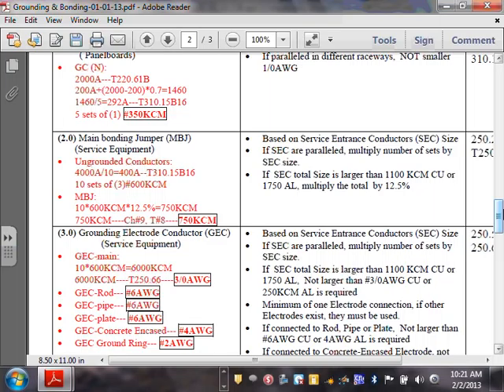Then you have to have a lot of fittings though. Clamps, I guess if you have a clamp, it's not a big deal. You just land it with a clamp. But remember, you're inside the bottom of the switchgear, and the bottom of the switchgear is open. So really, the hardest thing when you're dealing with 750 is if you pull it in a conduit. If you're not pulling in a conduit, you're working in the bottom of an open switchgear. It's not as hard as pushing it through a conduit.